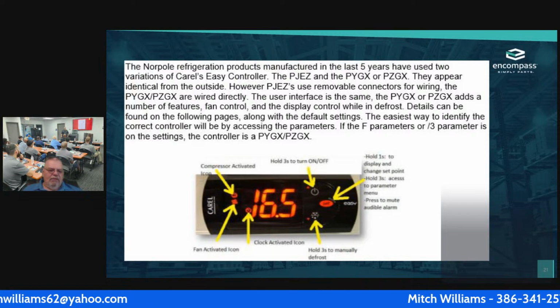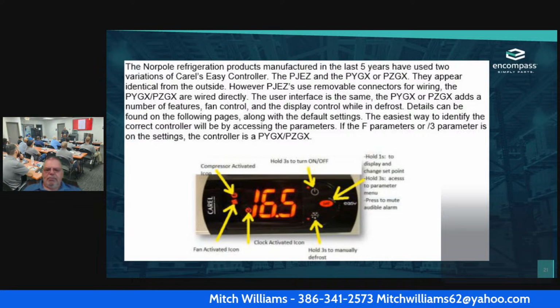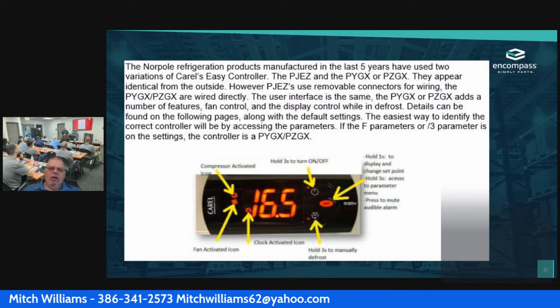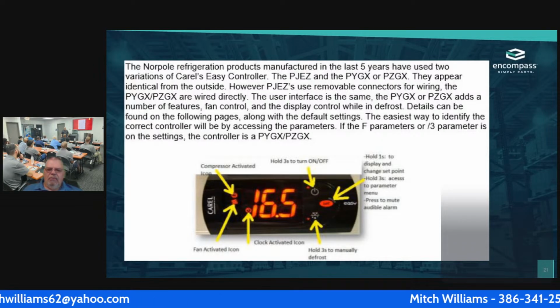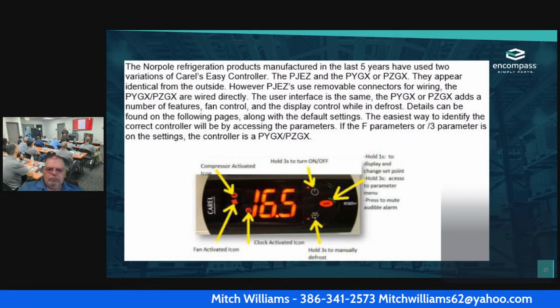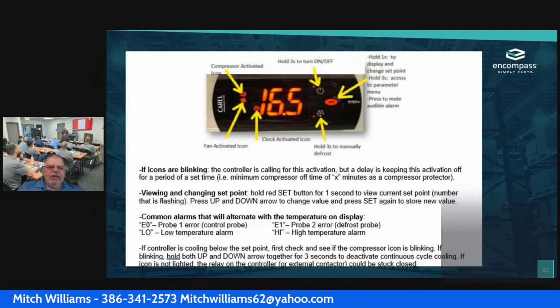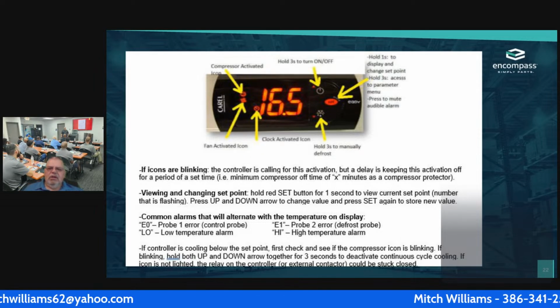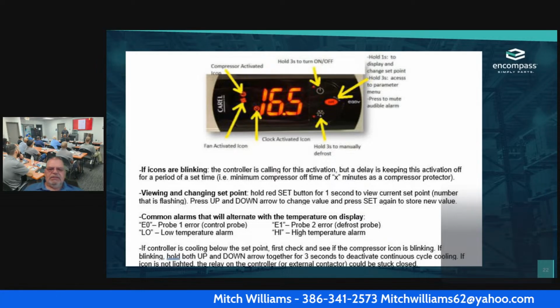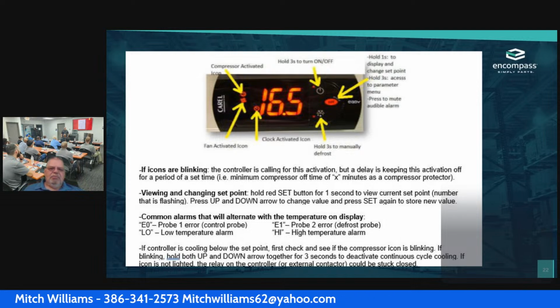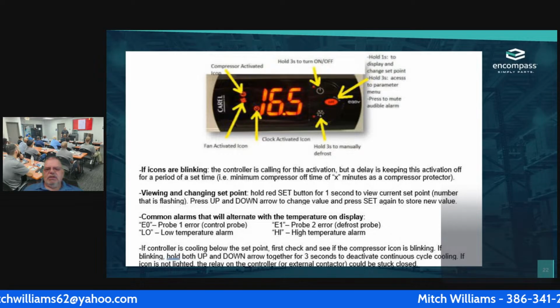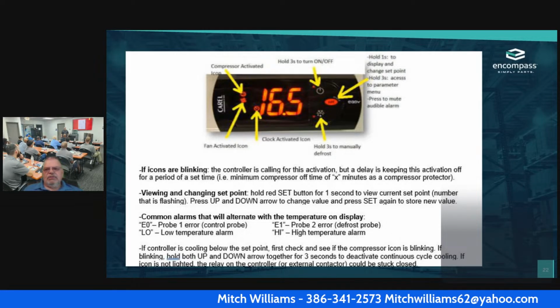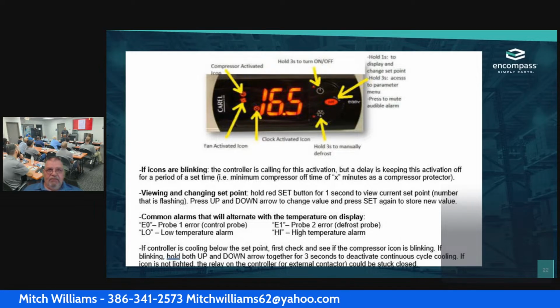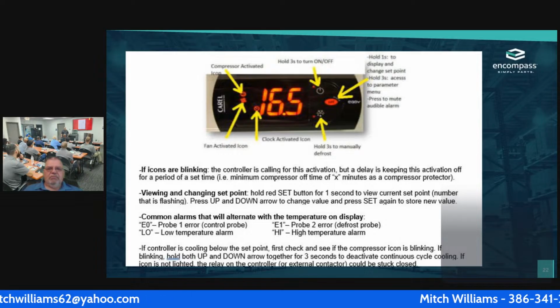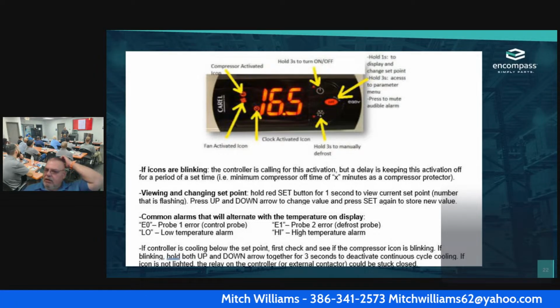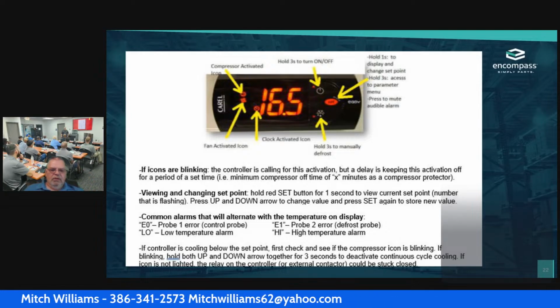If I just push it again, it mutes any audible sound if I do a quick press on it. Okay. Then if you look on the very bottom right there, if we hold it for the whole 3 seconds, you can enter the defrost manually. Okay, so if the icons are blinking, the controller is calling for activation, but a delay is keeping this activation off for a set period of time. The minimum compressor off time is, depending on what you have it set on, X number of minutes as a compressor protector. You know, it's the same way with many of the ice machines out there. They have a 3 to 5 second delay, and that keeps the unit from just dumping everything on, which causes a huge overload of the amperage.